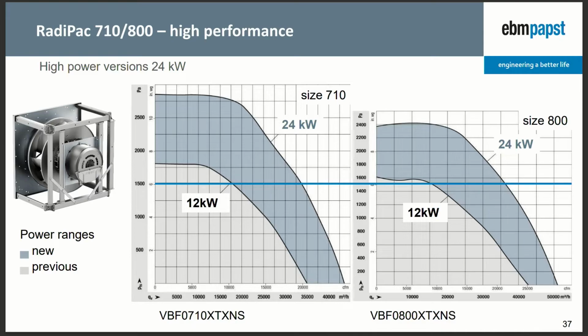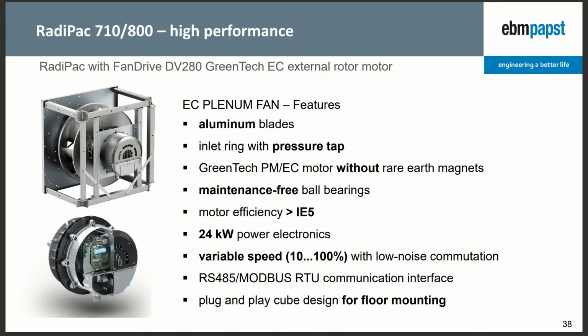where we can now create higher speed. Before, we had the limit at 12 kilowatt, and the gray area here is what we add to these diameters. So you see that we can run up to 2,500 pascals. So in applications like make-up air handling units, in clean rooms, or in pharmaceutical environments, or also in ventilation units where you have long duct systems and dense filters, this product can be used. And here, same thing, we come with all the features you know from what was explained before. We also have the integrated vibration sensor and high efficiency. This motor has about 95% efficiency.